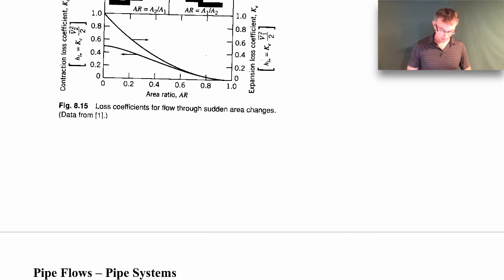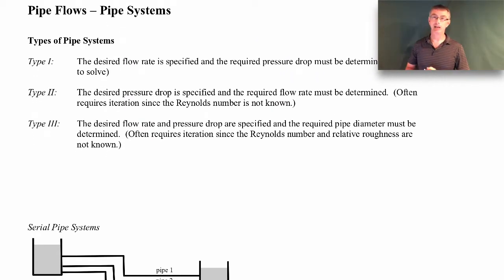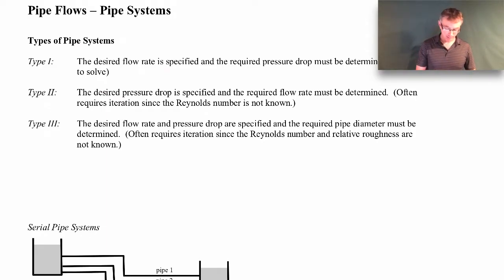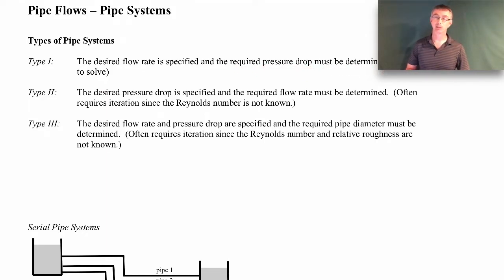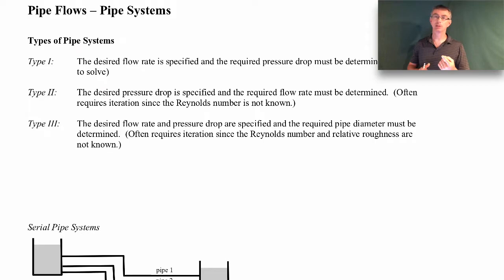Now let's talk about the different kinds of pipe systems we come across, classified as Type 1, Type 2, and Type 3. Type 1 pipe systems are ones where we're given the flow rate and have to determine the pressure drop. These are the easiest to solve because you know your pipe diameter and flow rate, so you can easily calculate the Reynolds number, the relative roughness, find your friction factor, and use the extended Bernoulli equation straightforwardly.